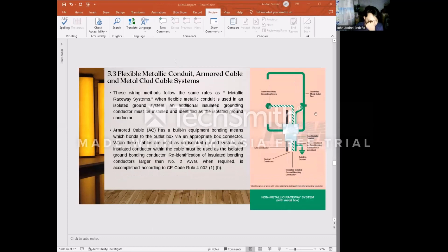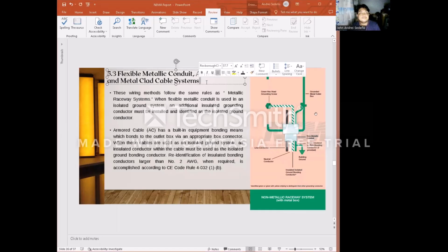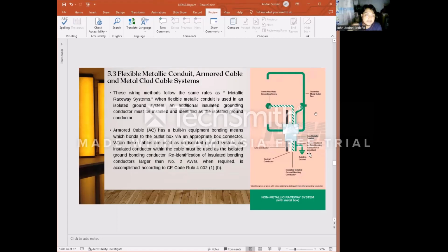Next is flexible metallic conduit, armored cable, and metal-clad cable systems. These wiring methods follow the same rules as the metallic raceway system. When flexible metallic conduit is used in an isolated ground system, an isolated grounding conductor must be installed and identified as an isolated conductor.